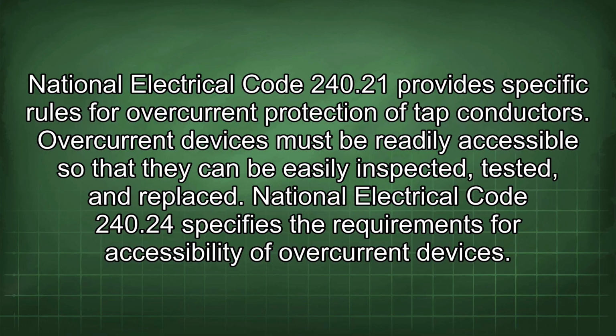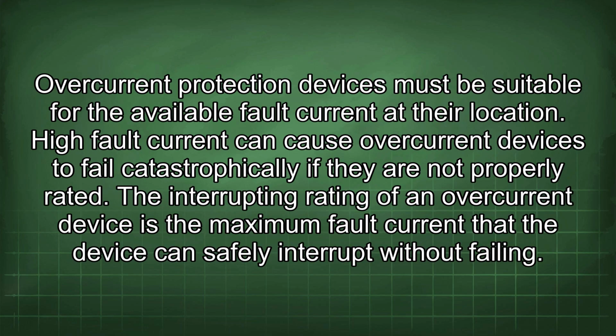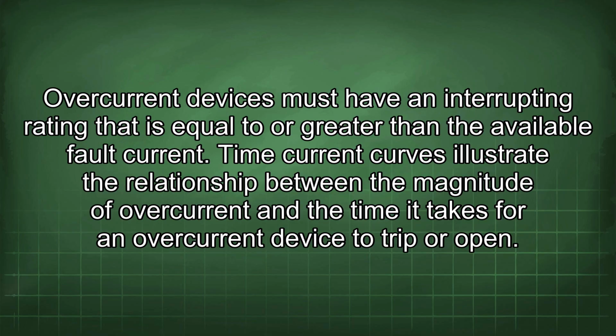Overcurrent devices must be readily accessible so that they can be easily inspected, tested, and replaced. National Electrical Code 240.24 specifies the requirements for accessibility of overcurrent devices. Overcurrent protection devices must be suitable for the available fault current at their location. High fault current can cause overcurrent devices to fail catastrophically if they are not properly rated. The interrupting rating of an overcurrent device is the maximum fault current that the device can safely interrupt without failing. Overcurrent devices must have an interrupting rating that is equal to or greater than the available fault current.